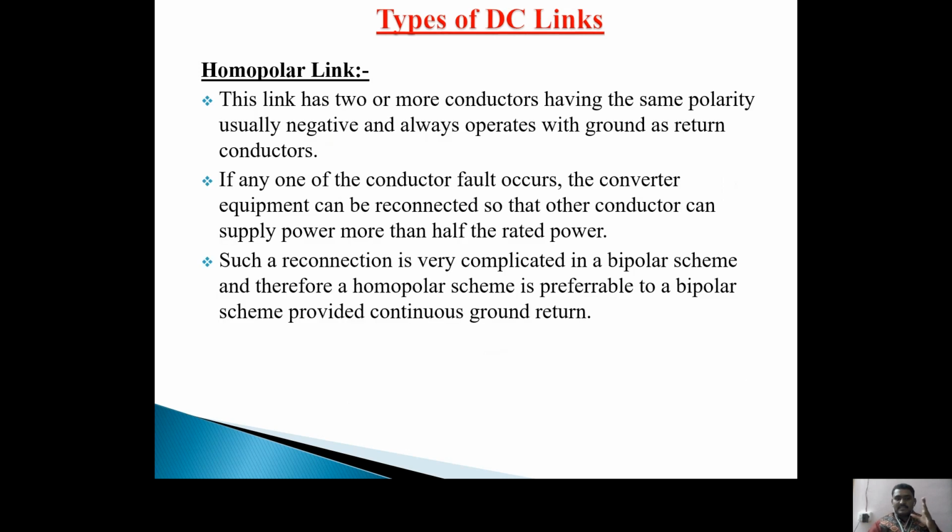so here this homopolar link has two or more conductors having the same polarity, that is negative, and always operates with ground as the return conductor. So if a fault occurs in any one of the conductors, the converter equipment can be reconnected so that the other conductor can supply more than half of the rated power.